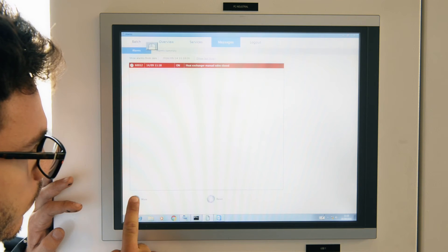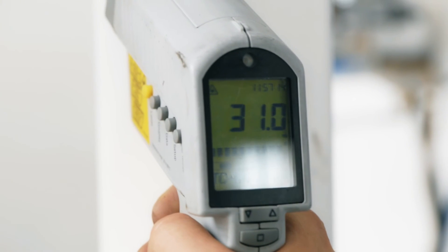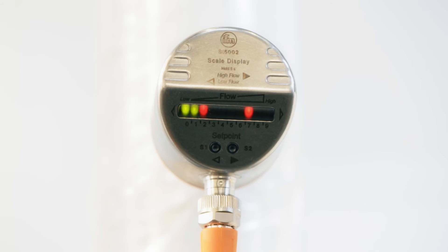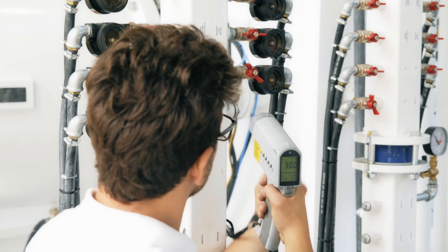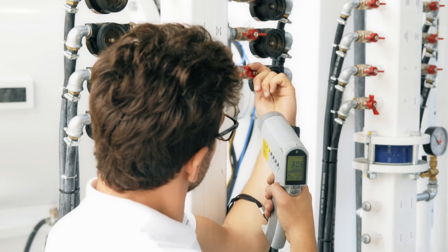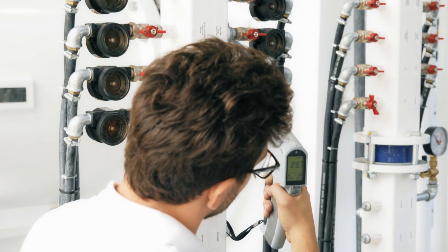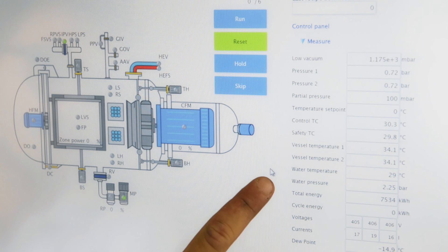For proper operation of the cooling system, the water flow calibration is critical. Since it is not possible to detect the temperature through direct contact with the water, you will need to use an infrared thermometer that, with IR aimed at the pipes, will give you a real measure of the temperature of the water in the drain. After reading the temperature, the operator can intervene on valves of the individual circuits by increasing or restricting the flow of water, so that the final temperature of each circuit is the same.